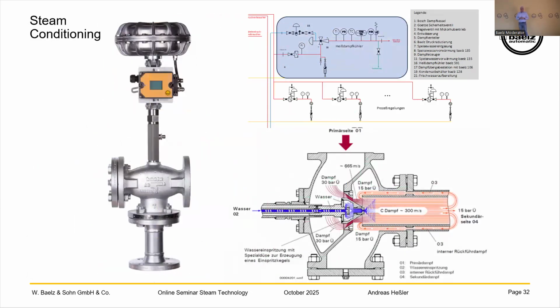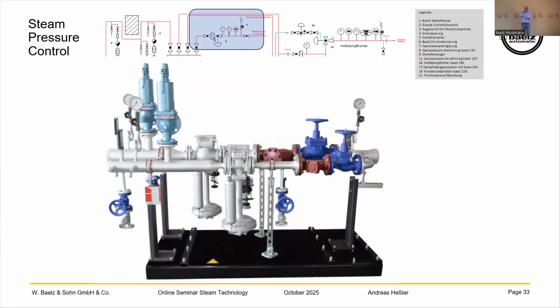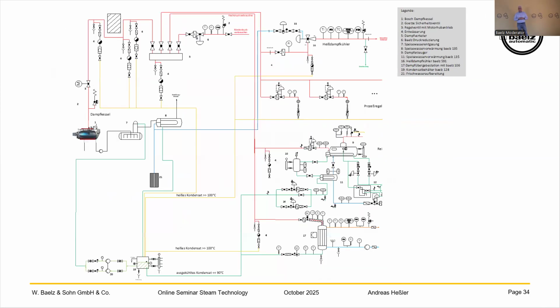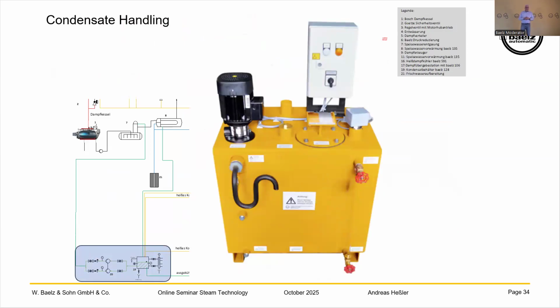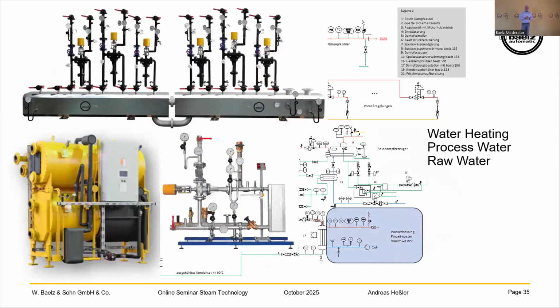The next would be steam conditioning. We have our 591 steam converting valve. I will say a little more about steam conditioning later on, when you will see more information. Then we have normal steam pressure control, in this case with our self-operating valve. It could also be done with a normal control valve. For condensate handling, you need some instruments and systems, which we can also deliver. You see, we are all around the complete circuit. When you go out on the steam and water heating side, we have the chiller and the divider, so we can deliver all the other parts on this secondary side also.